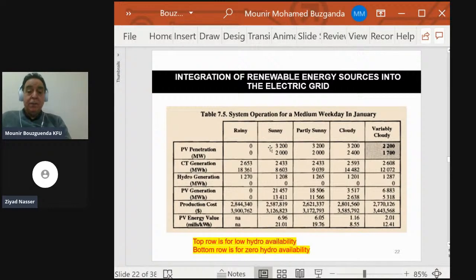Just to give you an idea, this top one is when you have, this is low. I think I reversed this. Well, actually, I didn't. Sorry. This is low hydro, meaning the 20% hydro. When you assume no hydro is available, again this is a hypothetical case, the acceptance of the PV dropped from 3,200 megawatt to 2,000 megawatt. That's a loss of 1,200 megawatt. Same thing here, almost the same. And then for the cloudy case, it accepted only 1,700.